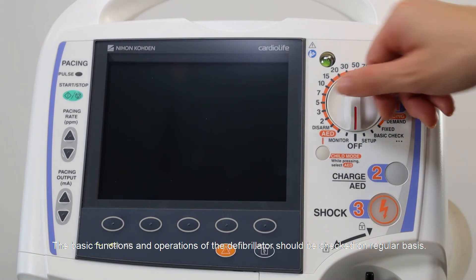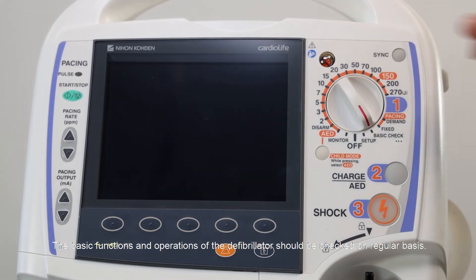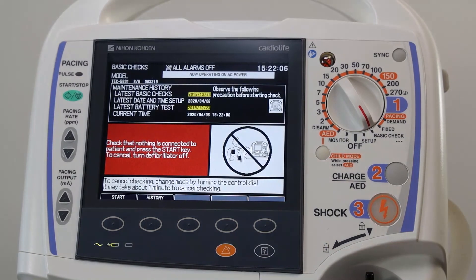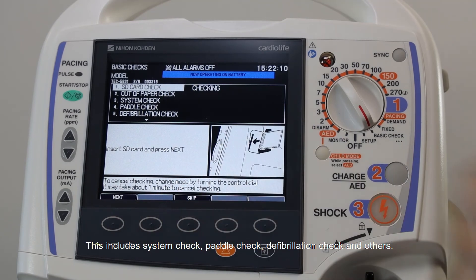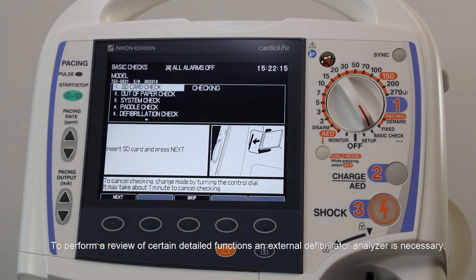The basic functions and operations of the defibrillator should be checked on a regular basis. This includes system check, paddle check, defibrillation check and others. To perform a review of certain detailed functions, an external defibrillator analyzer is necessary.